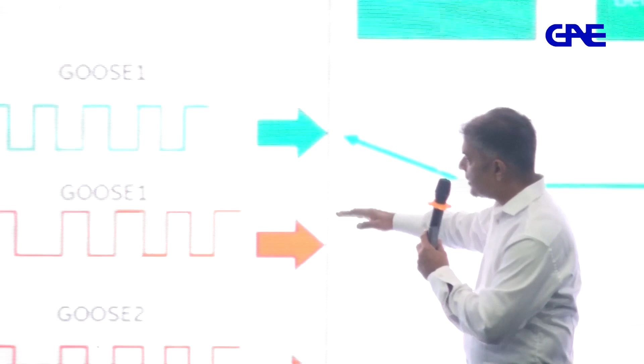So simulation mode, what it is that you have your GOOSE messages published from the devices. This is your subscribing device, so it is subscribing to all the GOOSE messages. Now you are connecting your test equipment, which is producing the GOOSE message like this. At this moment your device is not in a simulation mode. The moment you put it in simulation mode, what will happen is that it will start subscribing to the signal given by the test equipment. So in this case all you need to do is to change the simulation mode.